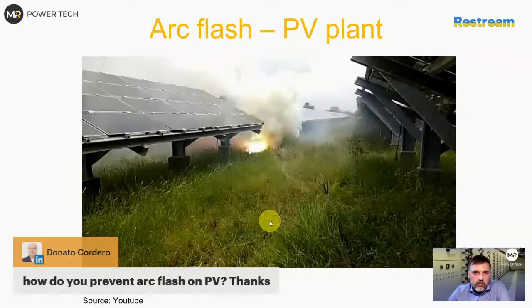So the problem is that if you cannot detect it, the inverter might switch off. It doesn't matter, the protection somewhere before might switch off, it doesn't matter, you still have a source. Power is coming to the point where the arc flash is happening, and at this point you cannot do anything. It will keep going until it burns, probably the whole panel or at least the cable. You just have two options: it will keep burning, or it will burn out and stop. So it is a problem.